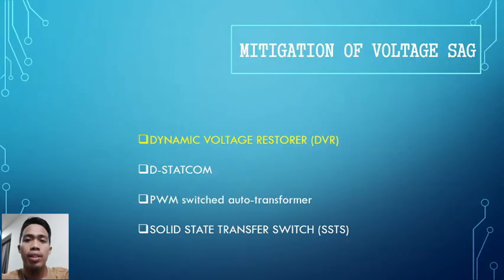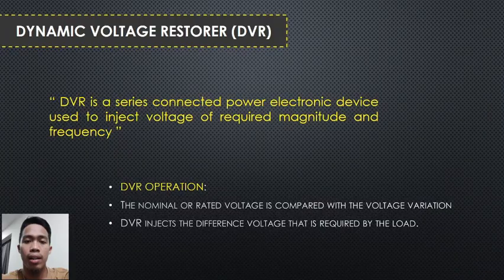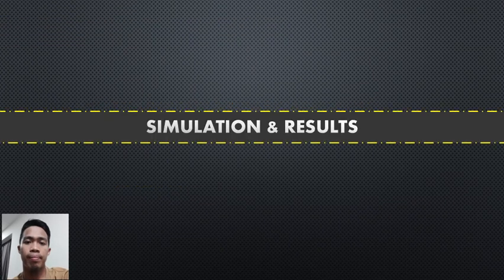For the mitigation of voltage sag, we have 4 techniques here. We will focus on the first one, which is the dynamic voltage restorer, DVR. So what is DVR? DVR is a series connected power electronic device used to inject voltage of required magnitude and frequency. In DVR operation, the nominal or rated voltage is compared with the voltage variation. DVR will inject the difference of voltage that is required by the load. So next we will go on to simulation and results.